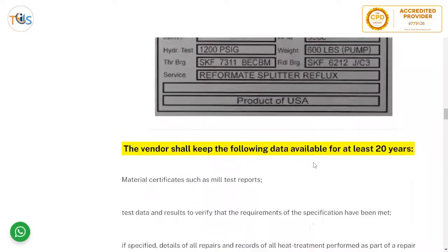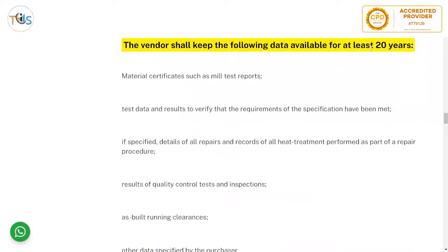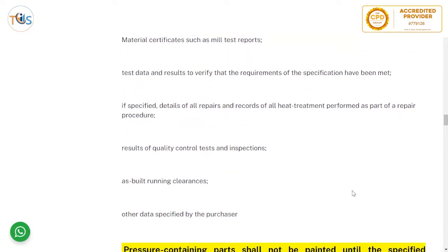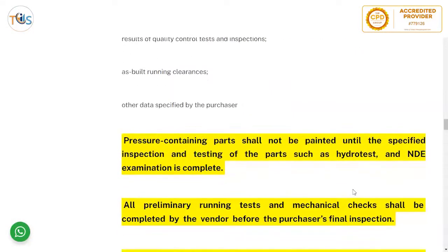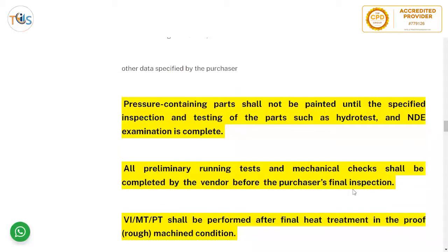The vendor shall keep the following data available for at least 20 years: material certificates such as mill test reports; test data results verifying specification requirements; details of all repairs and heat treatments performed; results of quality control tests and inspections; as-built running clearances; and any other data specified by the purchaser. Pressure-containing parts shall not be painted until specified inspection and testing — such as hydrostatic test and NDE examination — is complete.